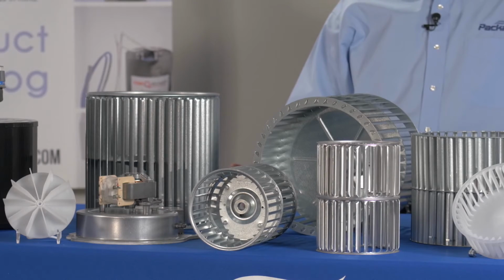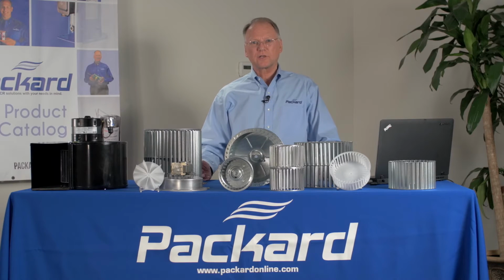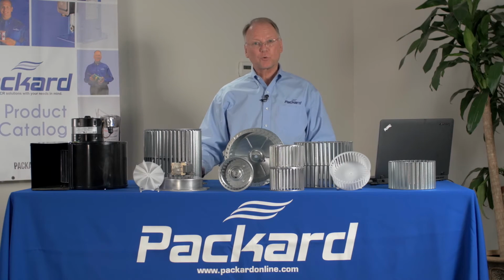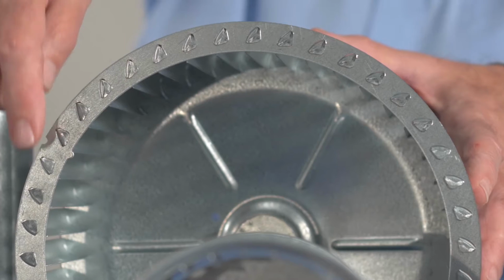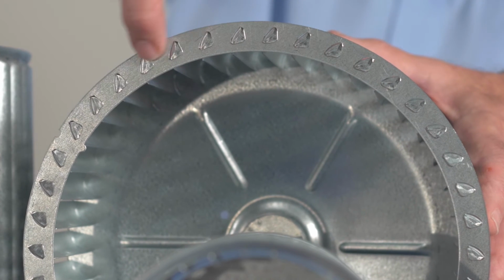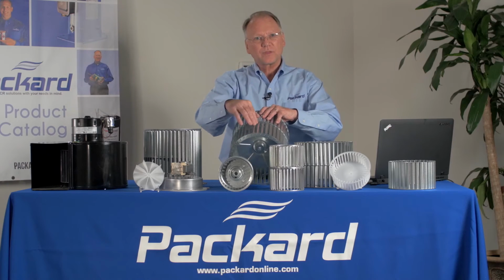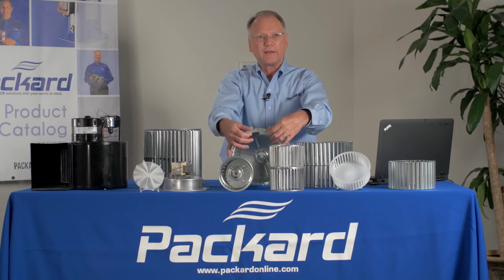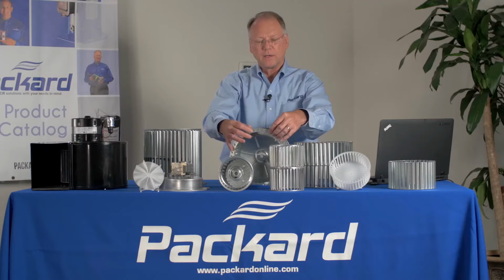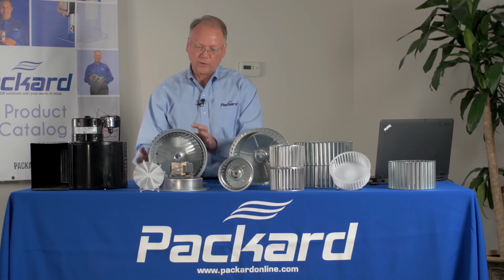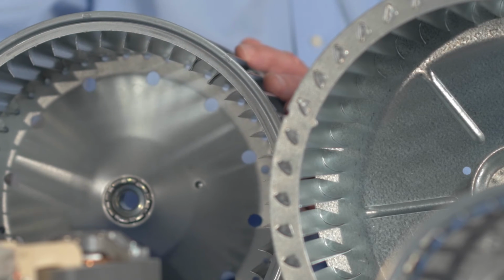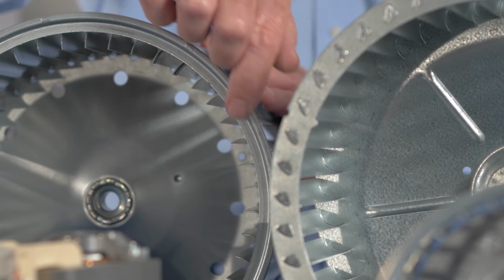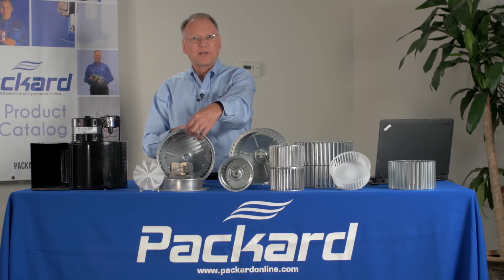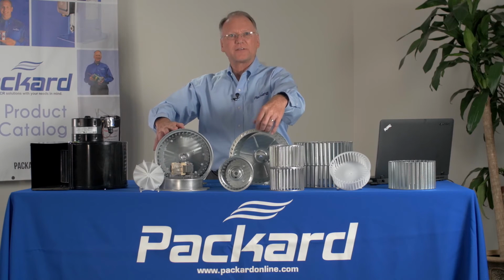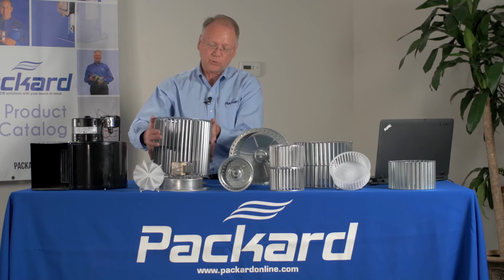When there's no cross-reference that's been identified, then we look at the characteristics of the wheel to determine a suitable replacement. One of the first characteristics that we look at is the actual construction of the wheel. In this case, this is what's known as a tab lock wheel. You can see how the blades of the wheel are inserted into a ring and locked into that ring. Another design is a strip wheel. With the strip wheel, a flat sheet of metal is used and it's punched out to give us the design that we need. The blades are not individually locked into the end rings of those blower wheels.